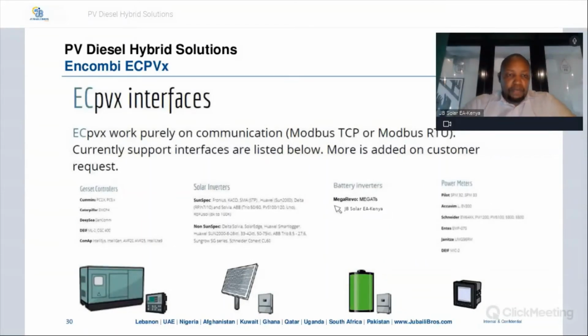So this is how the ECPVX interface looks like. It works purely on communication. This can be on the Modbus protocols, either TCP or RTU, and it supports interfaces listed below. This you'll be able to get once the webinar is over, and you can see it. You have different interfaces for the generator, for the solar inverters, for the battery inverters, as well as for the power meters, and more can be added on customer requests.